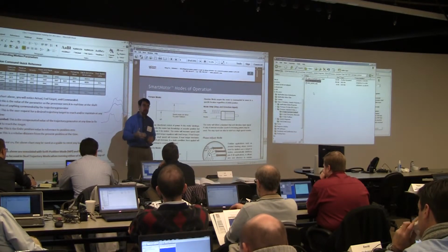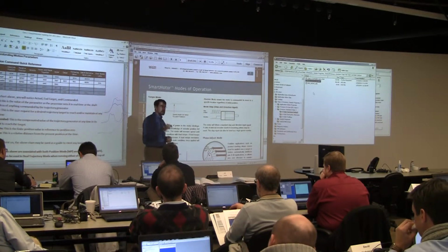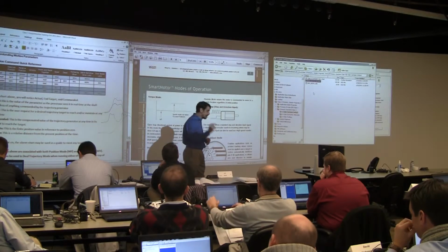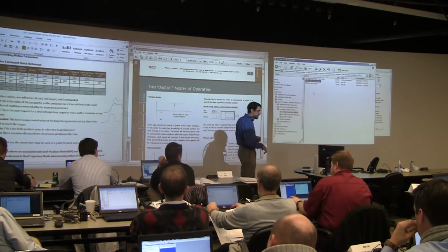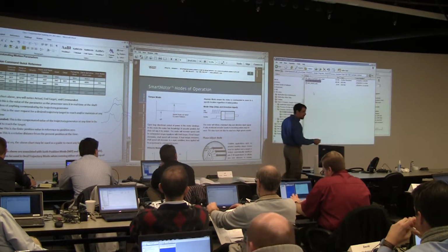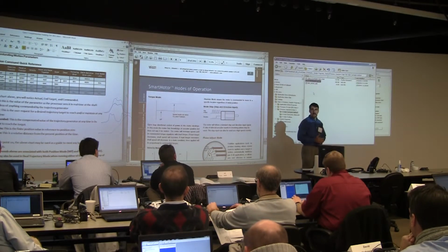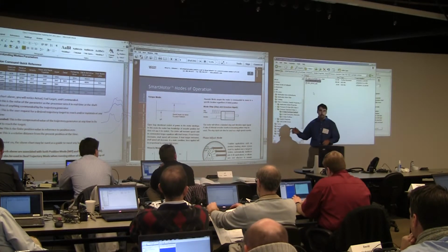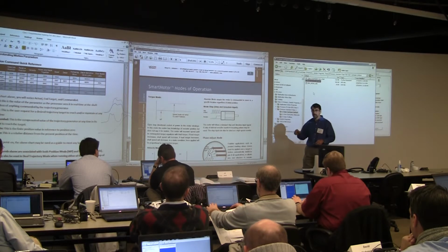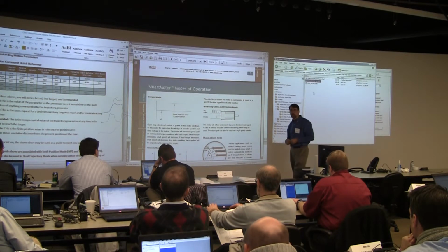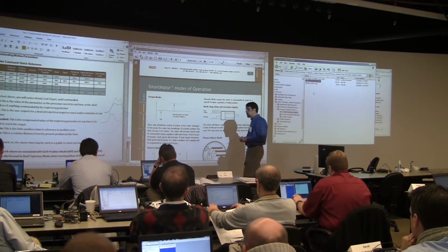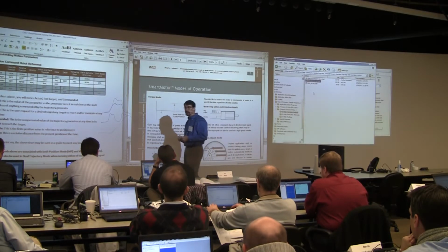At the tail end of the download, it does a processor reset. It basically goes offline, resets the processor, and powers it back up as if you had unplugged and plugged it back in. So when you go to download the firmware, at the tail end of it, you will lose communications with that motor. And then you'll have to go back into SMI and readdress and refind that motor.